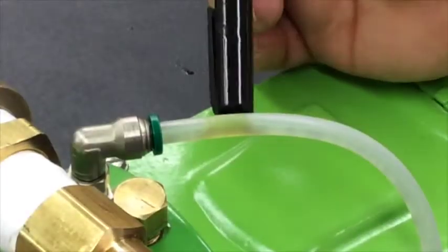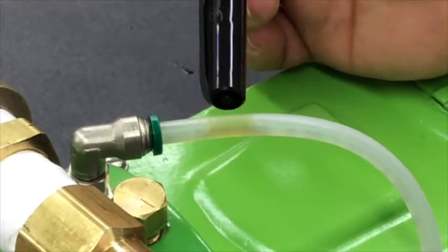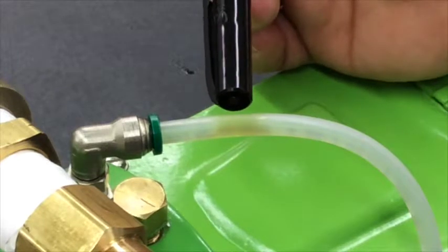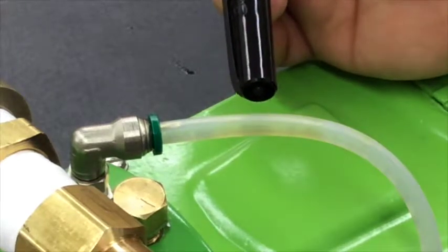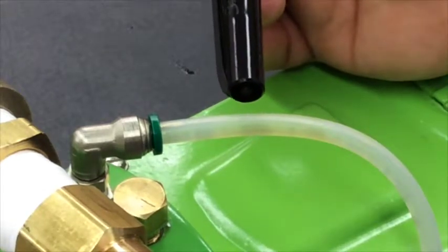All right, we've got this pump all back together. We're flowing water through it, and I'm pointing here to the air bleed valve, and you can see that little shot of oil bumping, and that indicates that the air bleed valve is working properly.